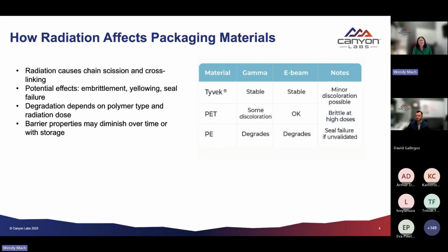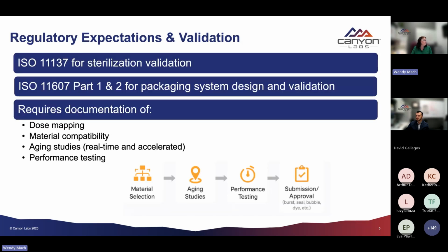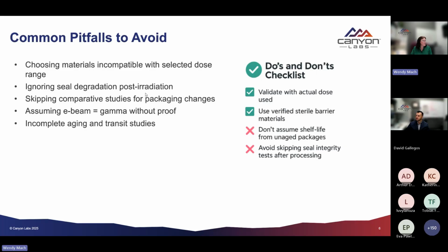Next, I'm going to talk about degradation. When we're looking at this in practical terms, Tyvek 1073 works really well for gamma and E-beam. When we're talking about co-extruded polyethylene structures, you're going to start seeing yellowing at doses above 35 kilogray. And with PVC and polycarbonates, you may have discoloration above 25 kilogray.